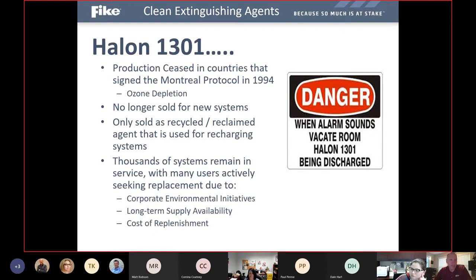And with that said, even though that all took place back in the mid-90s, there are still thousands of systems actively in service throughout the world, and many systems that do discharge, and there's still plenty of agent out there to recharge your systems with. The only caveat is we cannot design or alter any Halon 1301 systems at this point. So anytime an existing system changes, it's got to be replaced with a more present-day accepted agent. And we can't just redesign a Halon 1301 system.